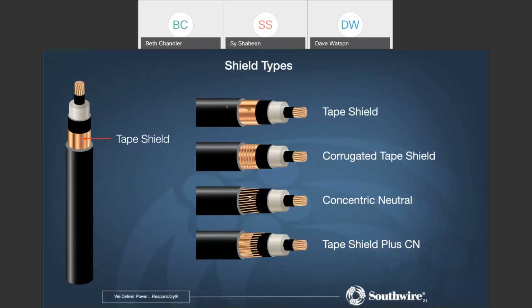And because it's dedicated to that transformer, normally there's balanced current between the phases, and therefore you really don't need a neutral return. While if you do want to protect your equipment and so forth, you can run a separate 600 volt THHN, green THHN, or XHHW along with the conduit. So this is a tape shield. It's really a 5 mil tape shield. It's pretty skimpy. It can't handle that much current. But again, understand that the reason for that is that it is not there to carry neutral return, but rather to bleed off the electrostatic charge.